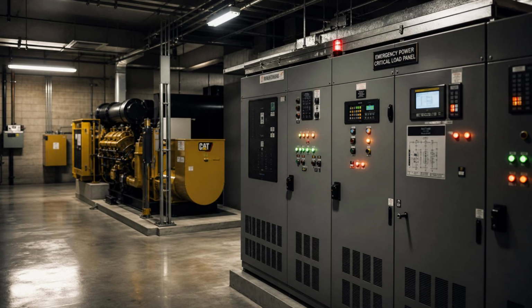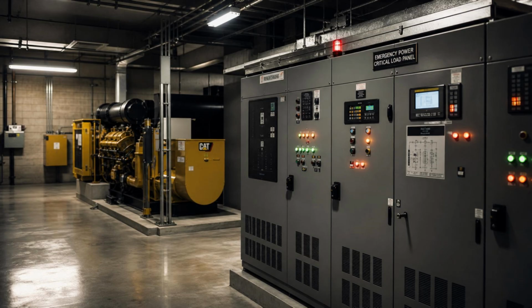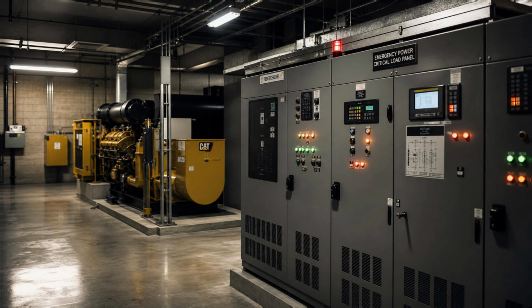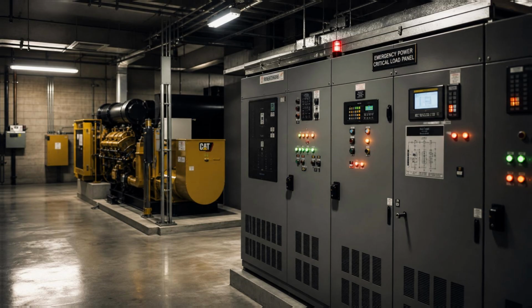The first and most fundamental branch is the life safety branch. The life safety branch exists for one purpose above all others: to ensure that in any emergency, a fire, a power failure, a mass casualty event, any disruption that might require the movement of people through the building or the response of emergency services, the physical environment of the hospital remains navigable and safe. This means the exit signs are lit, the corridor emergency lighting is on, the lighting in the stairs and the exit pathways is active, the fire alarm and detection system is powered. The systems that control smoke barriers and fire doors and smoke exhaust, the mechanical means by which the hospital manages the movement of smoke through its spaces in the event of a fire, these systems are energized and functional.